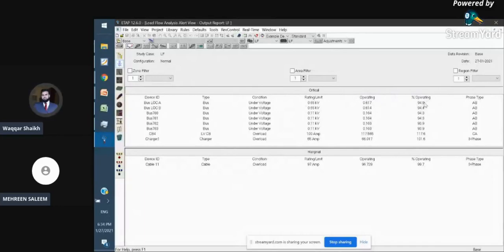Some alerts are marginal, like a cable rated for 97 amps that is running at 96.729 amps, filling its ampacity up to 99%, just near its limit. This gives us a marginal alert, so that if you don't want the cable to be damaged, you should keep its ampacity slightly lower than rated. Here we can see which equipment is approaching its limits and which is exceeding its limits with respect to their characteristics.